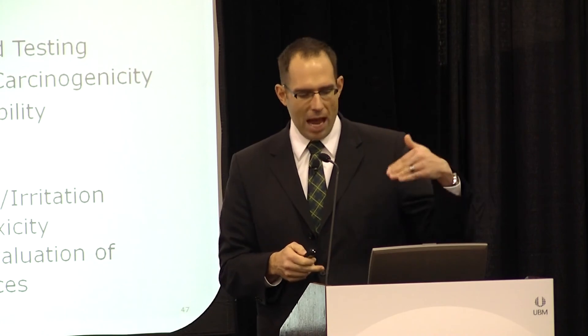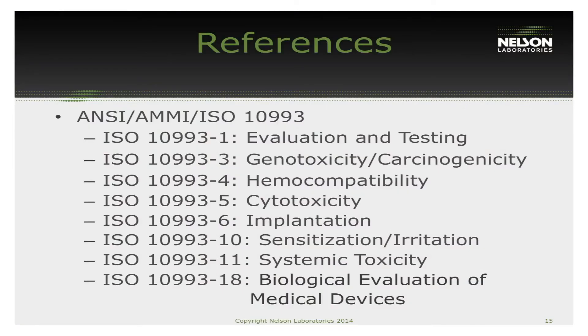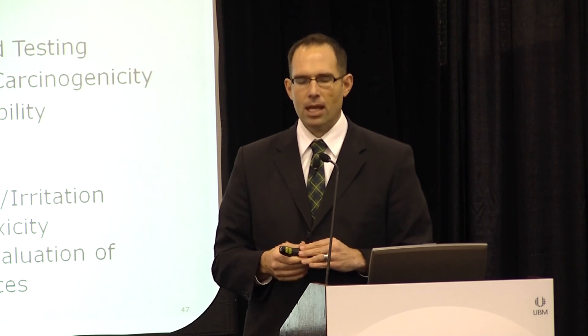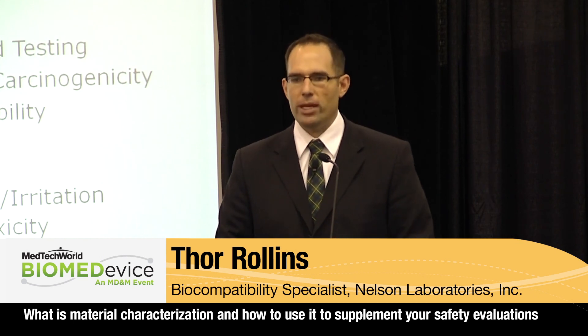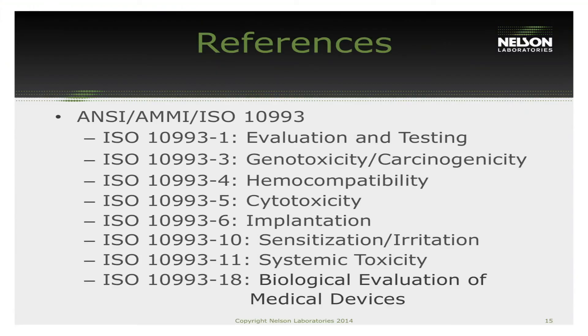We have been successful in running material characterization to help justify out of some biocompatibility tests, particularly around chronic toxicity and mouse micronucleus or genotoxicity tests, using chemistry and toxicological output to save time and money. In foreign regulatory arenas like Europe, this risk-based approach using material characterization data is much more successful for biocompatibility determinations.